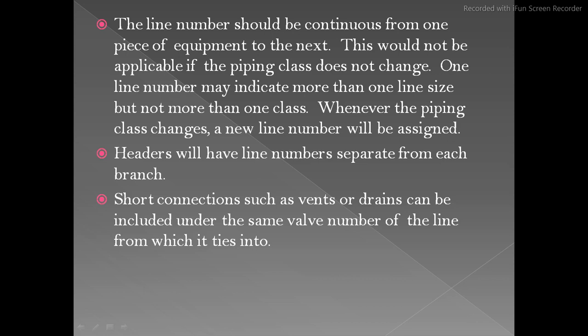When the line number changes, the piping class changes — you get a spec break and the line number changes. Headers have line numbers separate from each branch; a header has its own line number and it cannot be the same as any branch. Short connections such as vents or drains can be included under the same line number of the line from which they tie into.